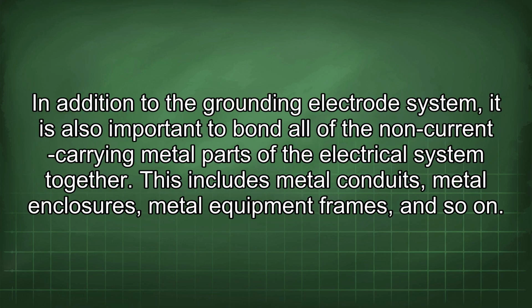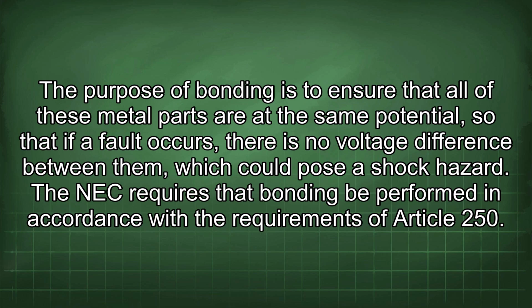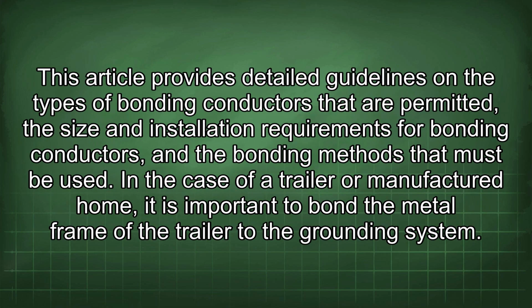The NEC provides tables that specify the minimum size of the grounding electrode conductor based on the size of the ungrounded conductors. In addition to the grounding electrode system, it is also important to bond all of the non-current carrying metal parts of the electrical system together. This includes metal conduits, metal enclosures, metal equipment frames, and so on. The purpose of bonding is to ensure that all of these metal parts are at the same potential, so that if a fault occurs, there is no voltage difference between them which could pose a shock hazard. The NEC requires that bonding be performed in accordance with the requirements of Article 250. This article provides detailed guidelines on the types of bonding conductors that are permitted, the size and installation requirements for bonding conductors, and the bonding methods that must be used.